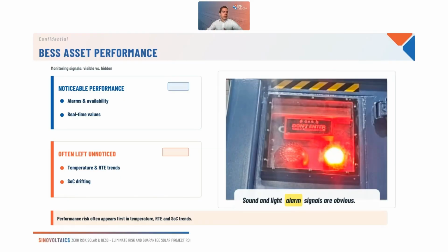But there's also a lot of things that often go unnoticed, that are difficult to read or interpret. These are often temperature trends or long-term trends, round-trip efficiency, how the voltages are behaving, state of charge of the system drifting, meaning the real state of charge is something other than what the BMS is saying. These small unnoticed things gradually become issues, and later on they can become noticeable performance topics, like the system is no longer available, or you cannot get the right amount of energy out, or you just have a short circuit and get an alarm.